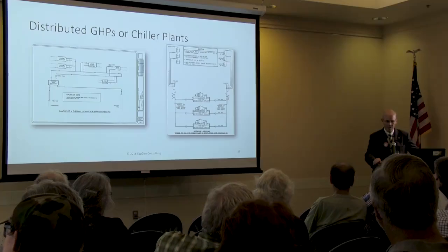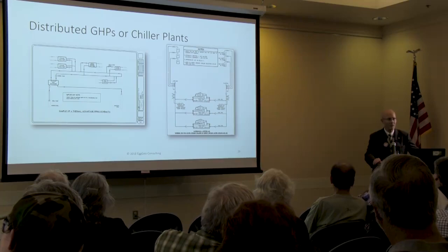I'm trying to recall exactly how this happened, but the bottom line was, they really didn't realize how much energy was being wasted and just going up the stacks from natural gas. They use a high energy steam driven chiller system. In other words, they are currently using natural gas boilers to make high energy steam to drive turbines that turn their chillers instead of electric chillers. So fortunately, I think that's on the road to recovery. But the amount of emissions from that is incredible.